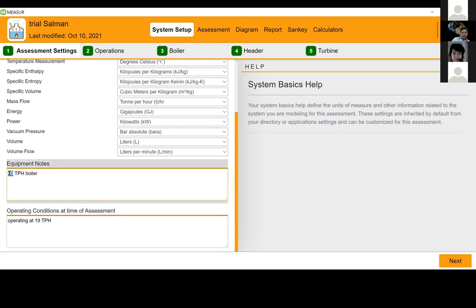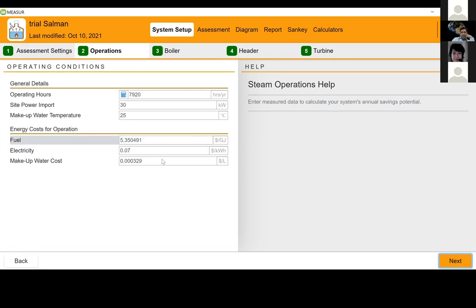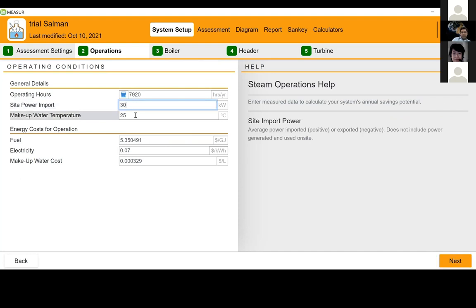For example, this one was a 30 TPH boiler but was operating at 19 TPH. Then we click next and it takes us to operations. Here we can set operating hours, how much kilowatt of electric power it is importing, that is what we can write here. Temperature of makeup water that we are adding.